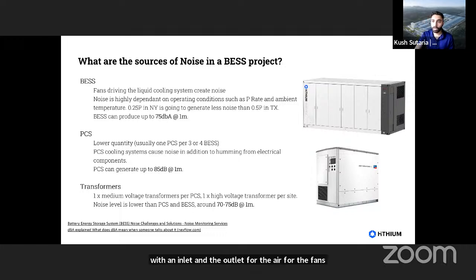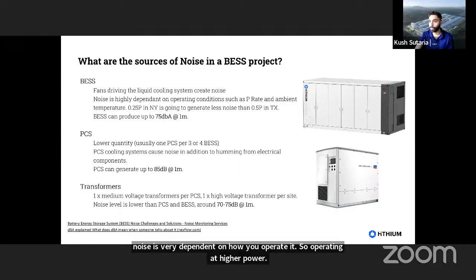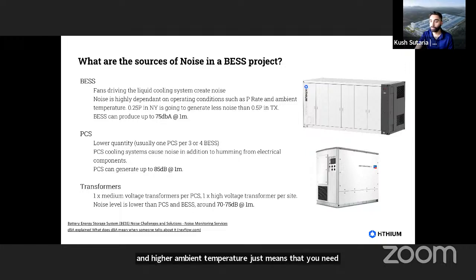The noise is very dependent on how you operate it. Operating at higher power and higher ambient temperature means you need to cool the cells more, which in turn increases your noise. So for example, you're going to get higher noise for a 2-hour project in Texas than a 4-hour project in New York.